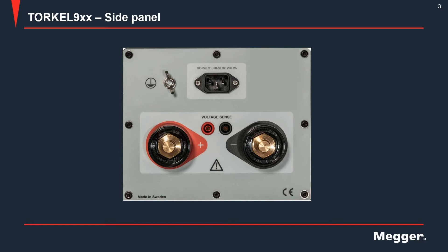This is what the side panel of the TORKEL looks like. On here you have an external ground terminal provided for added safety. This is where the AC power cord goes. This is where you connect the positive and negative current cables. And finally you have binding posts for connection of voltage sense leads if you use them.